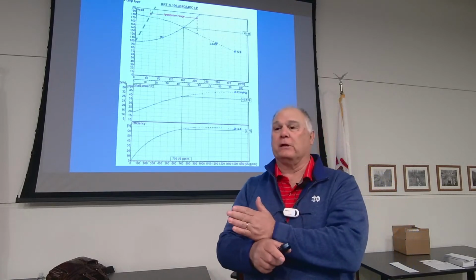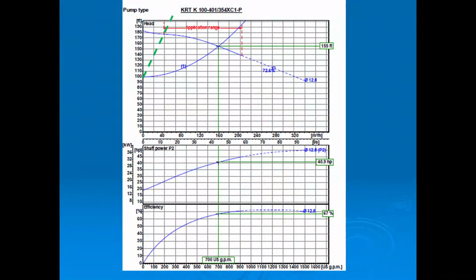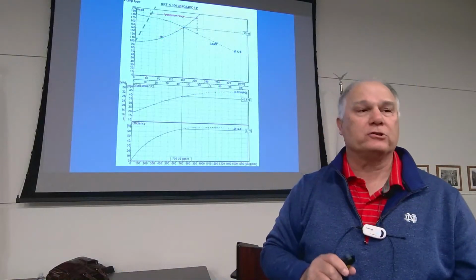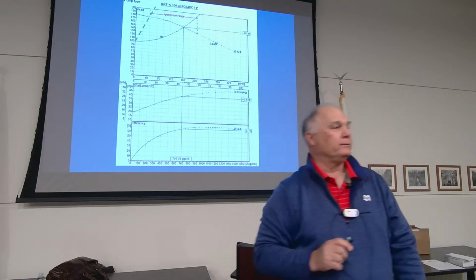So the computer is going to give you that, depending on how you select your programming, but most are going to be efficiency-wise. The top selection is going to be the most efficient pump, regardless of solid size. In this one, the efficiency is 67%, which is pretty good. Off to the right, you'll see that the line goes dashed. Why does it go dashed?